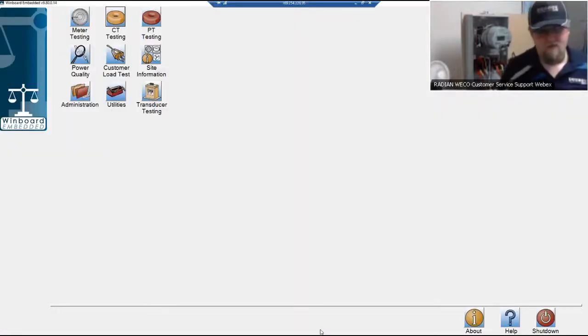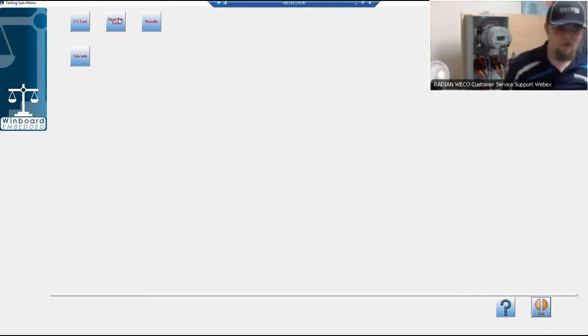Now we're going to transition over to software and talk about the software side of the RW and setting up your CT test after you have your secondary part of the hardware going. As you can see now on my screen, when you first boot up your RW, this is the screen you'll be greeted with. This is the main menu of the RW. And one of the options that you get is CT testing in the middle column, top row. If I click on CT testing and go into it, you get two options for CT testing.